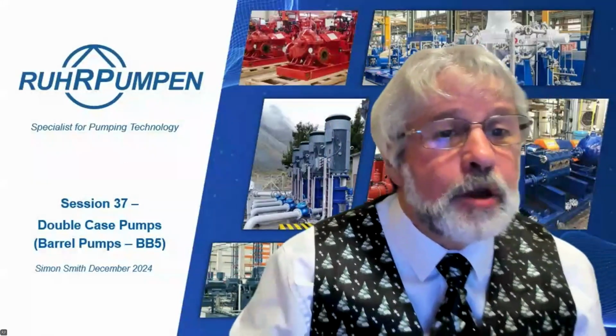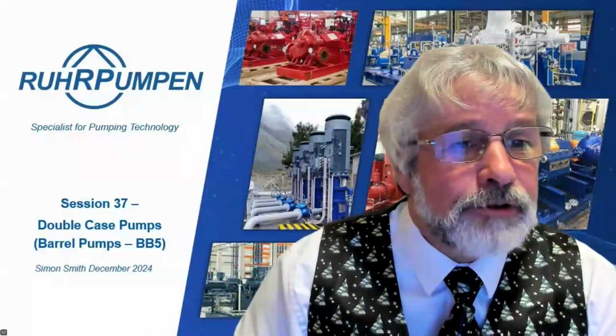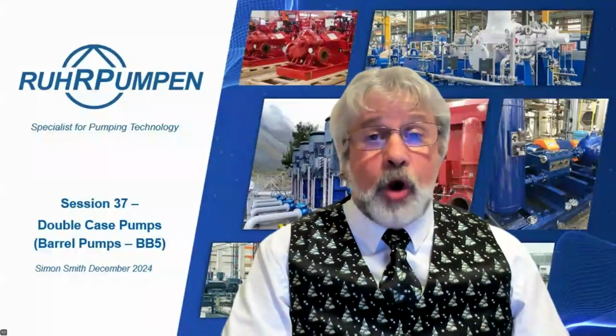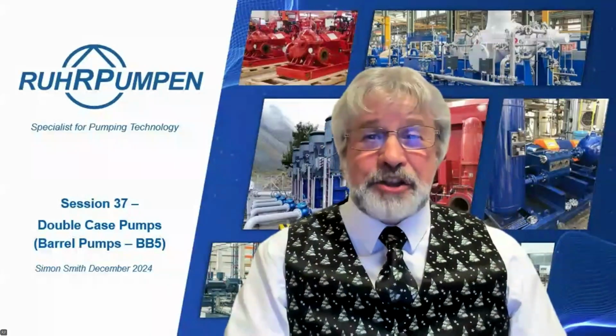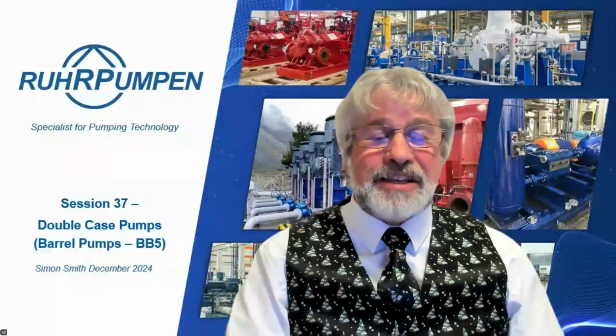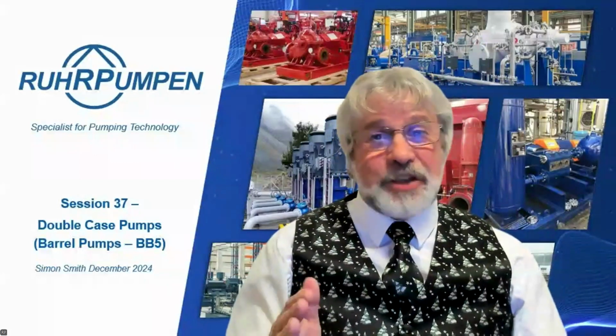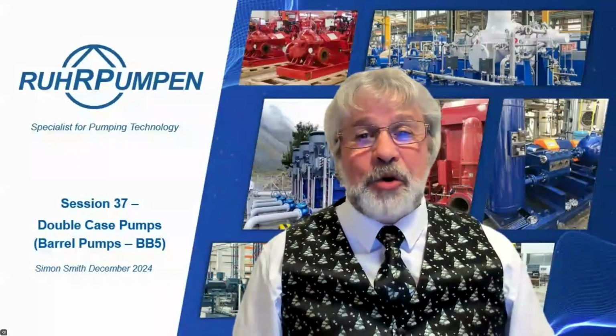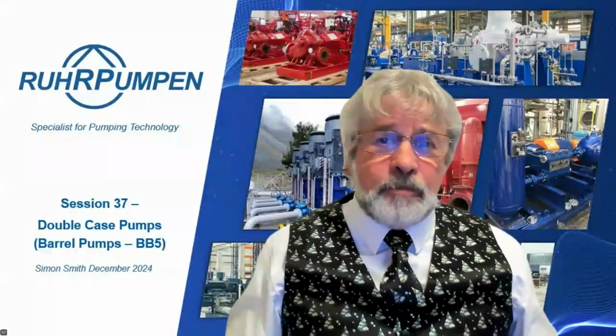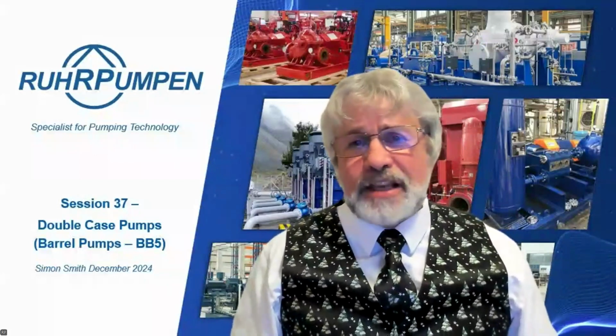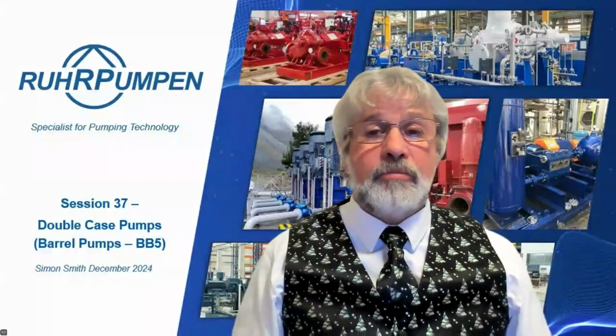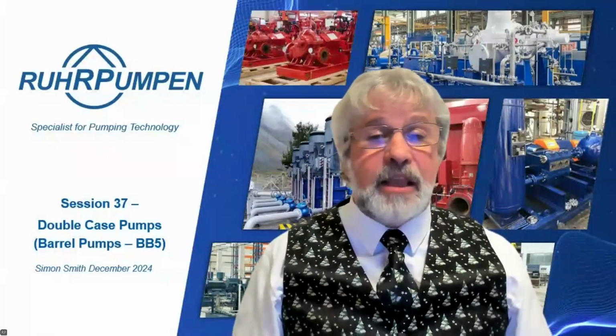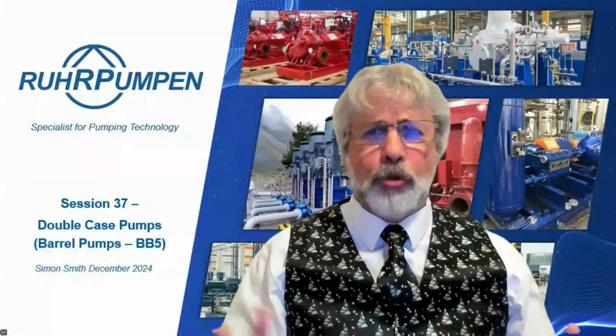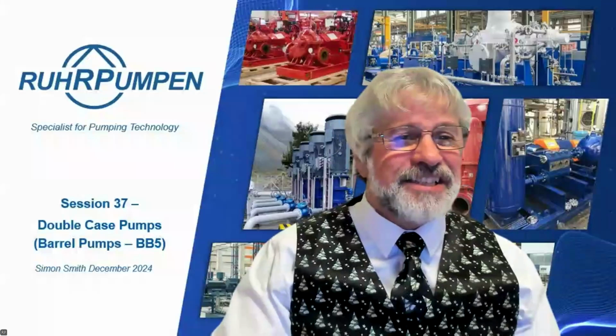Nalathambi Dharmalingam says, what's the maximum number of impellers available for BB5? How is the number of impellers decided during pump selection? Well, we optimize it. Ideally, we'll have impellers that are about 95% of their full diameter operating, and that will determine how many stages we need. We have gone up to 16 or 18 stages, I believe. Commonly, it'll be 8 or 10. Some customer specifications say no more than 10. There's no good reason for them saying that. They just don't like the idea of too many stages.